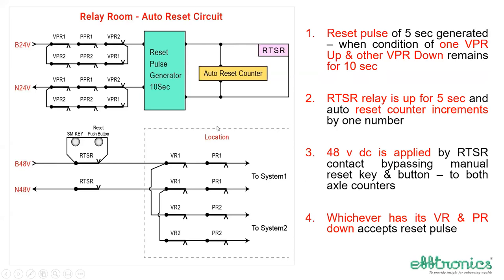What we are seeing here is that this dotted part is the location, and the remaining part is the station house, that is the relay room. In the relay room you have the VPRs and PPRs, which are repeated. The reset pulse generator takes input from them and picks up a relay, RTSR. The reset count is also increased, and then it applies the reset. You can see this is bypassed by the SM's key and reset push button, that means manual. The straight path is auto reset, and the loop one is the manual reset.